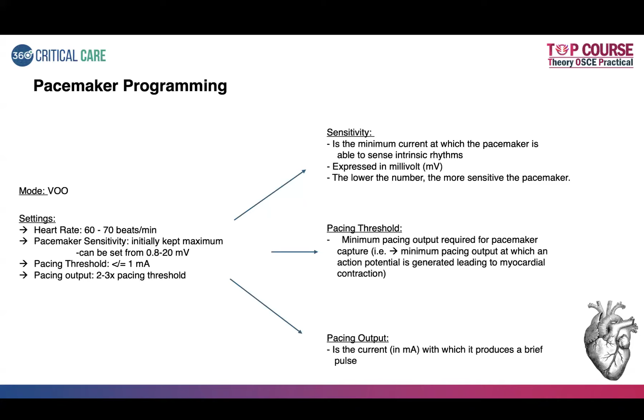Then the third important definition is the pacing threshold. The pacing threshold is the minimum pacing output required for the pacemaker capture. It is the minimum pacing output at which the action potential is generated, leading to a myocardial contraction. So for a pacing threshold, you need to have it at less than or equal to 1 milliampere. And the pacing output should be 2 to 3 times this pacing threshold. These numbers in the settings should be memorized because we do deal with a lot of patients on transvenous pacing. So you need to know how to manipulate the settings in the event of any chronotropic issues.